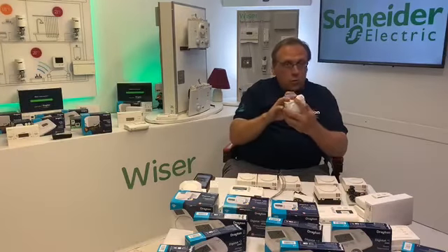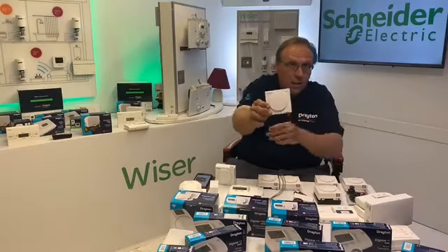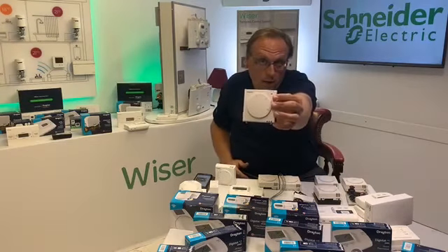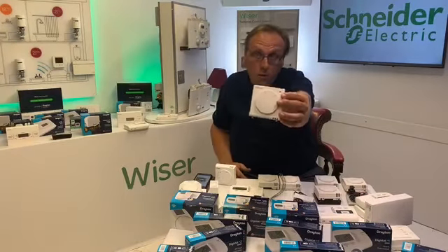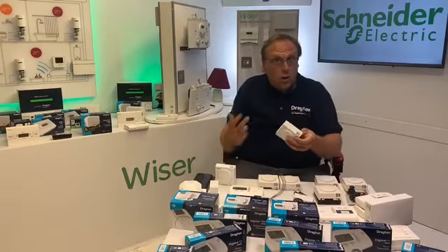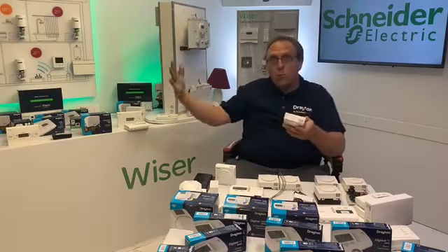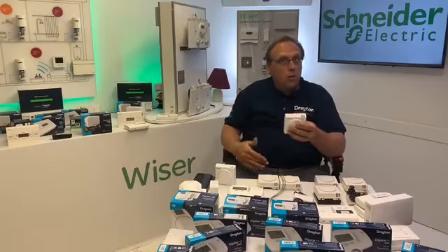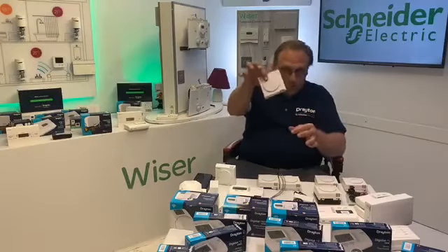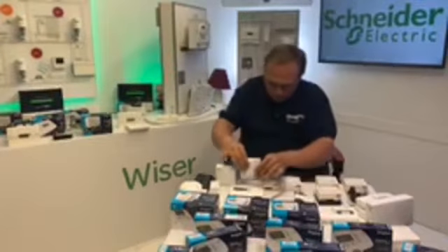So that's an RTS1. I'll move on to the RTS2, which is essentially exactly the same as the RTS1, except in the top corner here, you've got a little light that shows you if you're calling for heat. If there's a call for heat, that will light up. Again, it's mains powered, so it's got to have a live and a neutral. It won't be a permanent live because it will be the live that's downstream of the programmer. So you've got to have a live in, a neutral, and then your switch live out. So an RTS1 with an indicator is an RTS2.